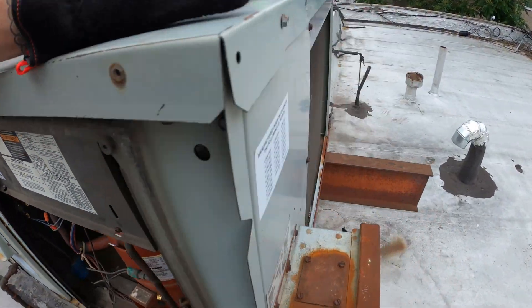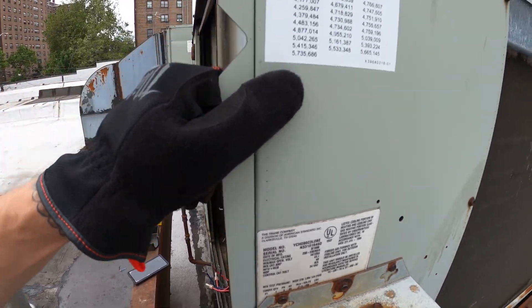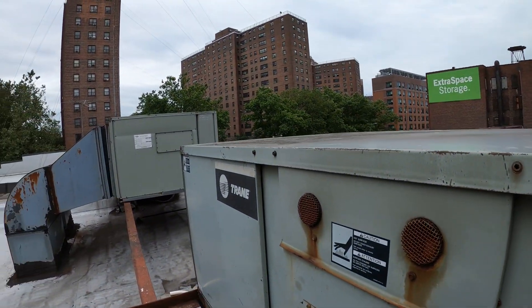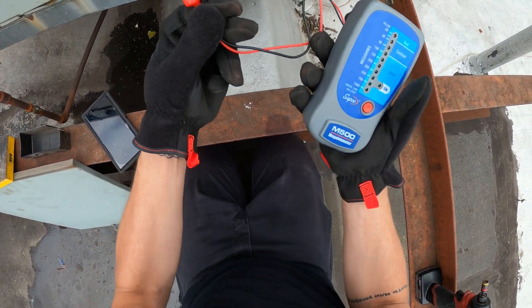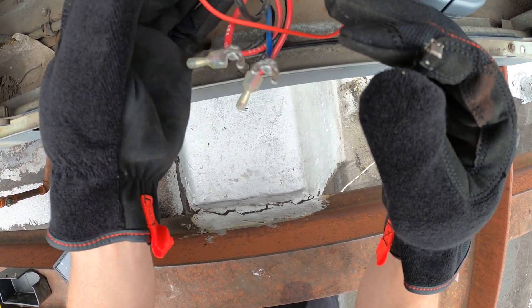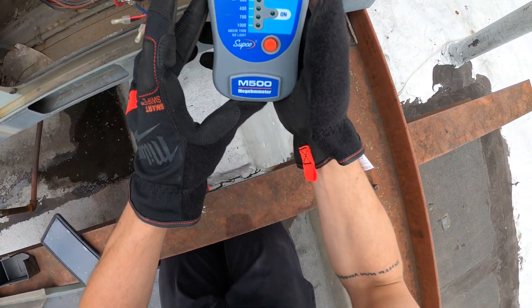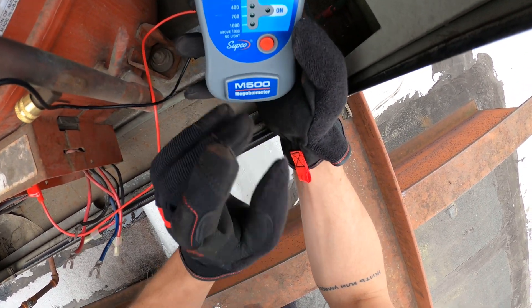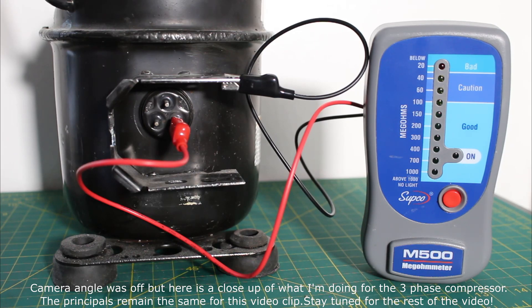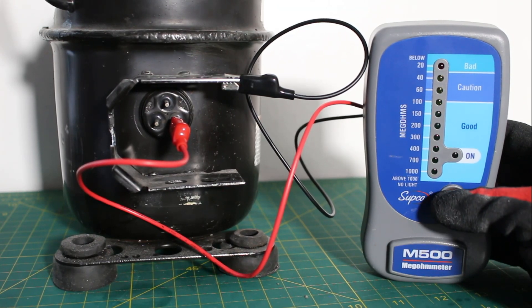Quick heads up: this unit is from 1998, which is unbelievable, and this looks like it's definitely the original compressor. Let's see how a Trane compressor holds up. Here's our megohmmeter — we have two leads. We're going to take one lead to our terminal; they're magnetic so you can just leave it there. The other one we put to ground. Make sure everything is holding. This is the easiest megohmmeter by far — all you do is press the button and follow the lights. We're going to go from one terminal to ground for each terminal.